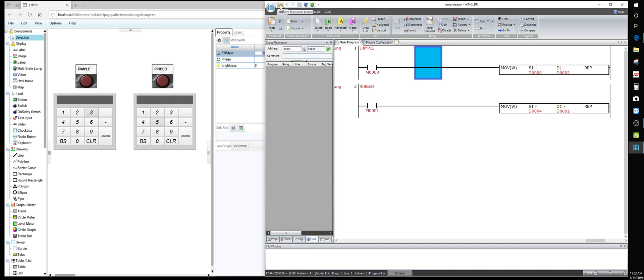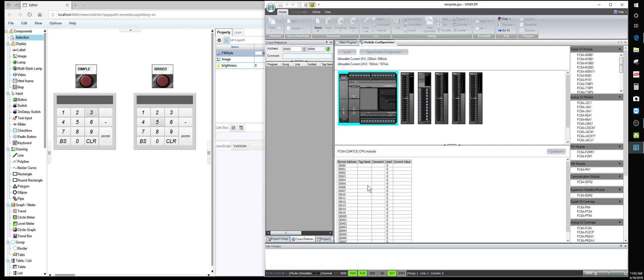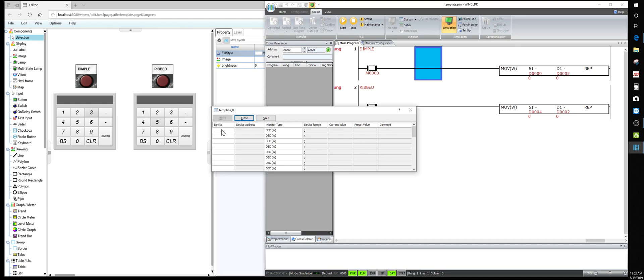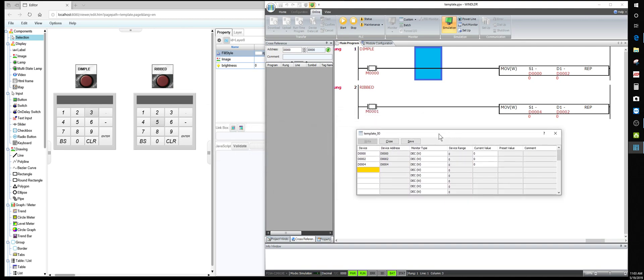Now let's go into simulation mode. I want to go online to the custom monitor and monitor D0, D2, and D4. I always do D0, D2, D4, D6 out of habit - I skip one every time in case I'm using a double word so I don't have to go back and work something in later. Always have extra data registers. This probably won't work yet and I'll show you why.